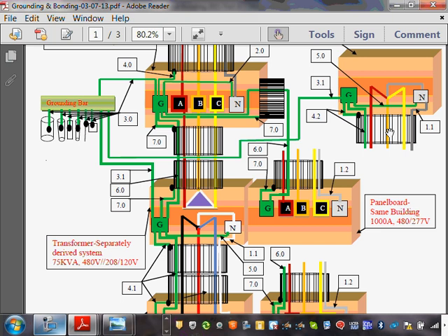Now, if your automatic transfer switch is after the service, you have a neutral in that service, and you bring three wires from the generator in there, you still have a neutral in your service. Good point. But now the service is out.